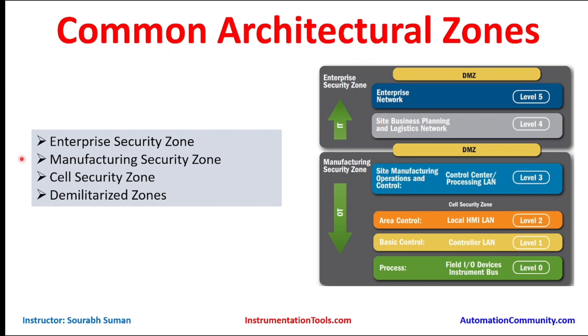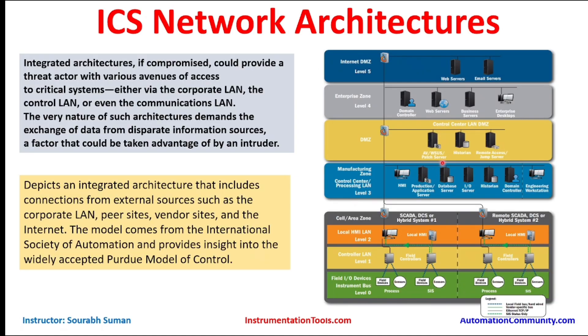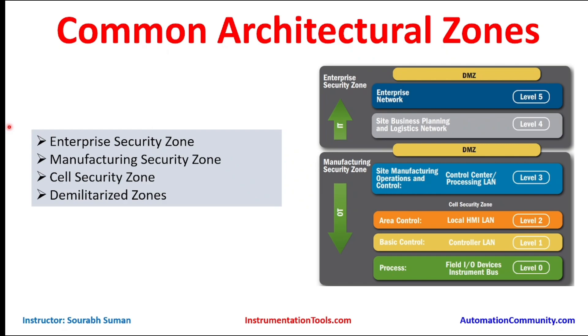The second zone is the manufacturing zone at Level 3, which contains the area where the vast majority of monitoring and control takes place. It includes production application servers, HMIs, databases, I/O servers, and historians. Operational support and engineering management devices are located here. The manufacturing zone is central to operations and provides required connectivity to the enterprise zone. It carries high priority and risk, so it must not be connected directly to any external system — a DMZ is required to filter and monitor all activities.